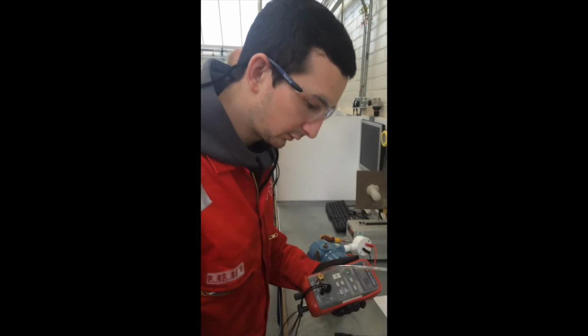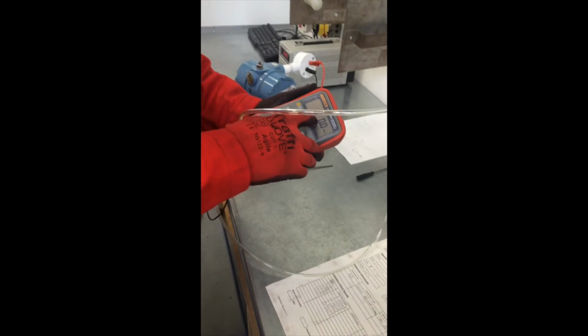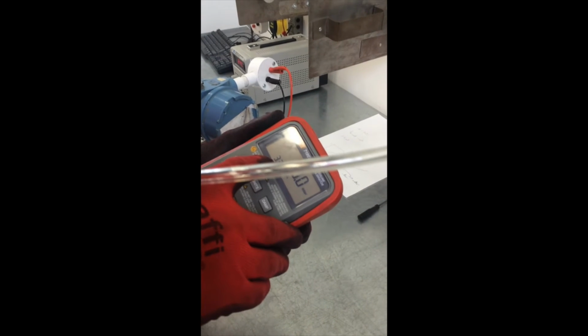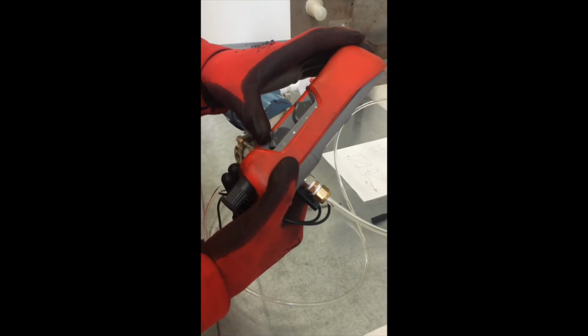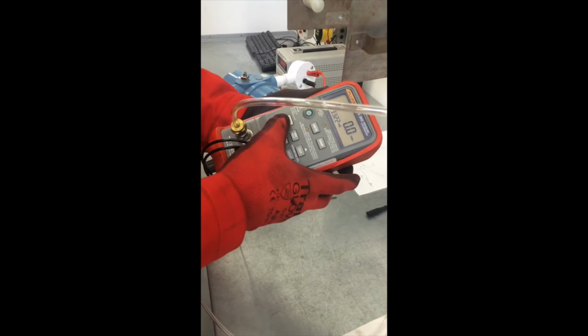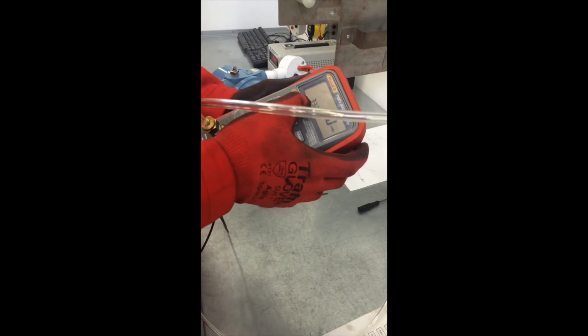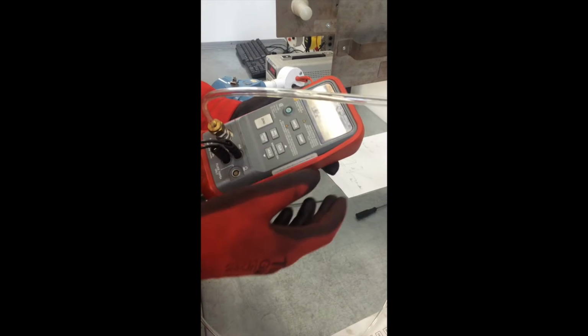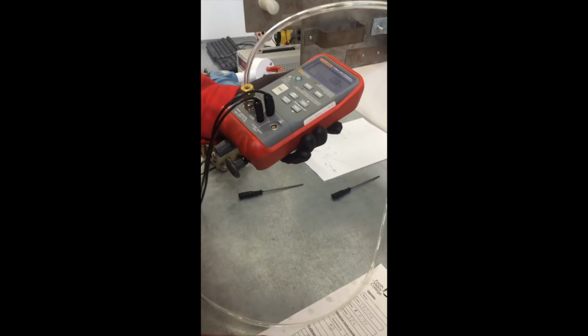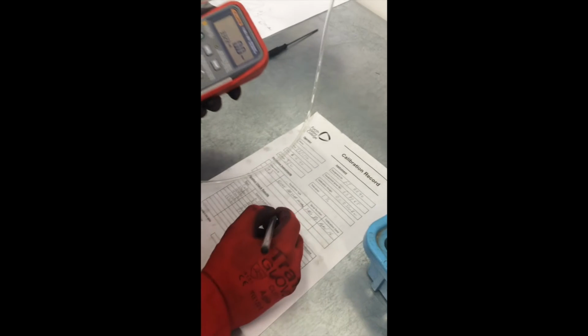So when you're doing your pre-calibration checks, you can already see here that it's at 0 millibar, it's reading 3.322 milliamps, and as you can see on my sheet here I've already prepared the expected outputs, so at 0 millibar it should be 4 milliamp. So what you do is you release the pressure by using this wee switch here, and then you close it again. You then zero the instrument to make sure it's reading 0, and then the 3.3 is the wrong reading. After that, you go to your first reading and write down your 3.32 as the actual output.